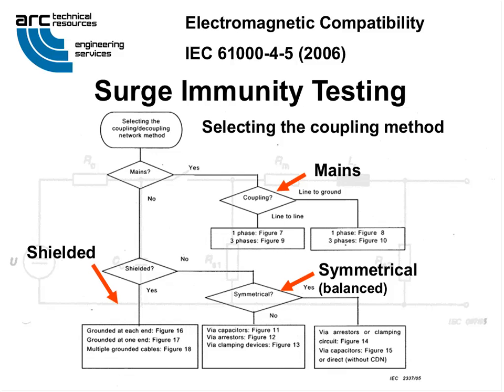The standard gives guidance on selecting the coupling method to be used. This agrees with Euronorm 55024 for computer equipment as well. Mains power is tested line to ground and line to line up to and including the test level specified. Symmetrical or balanced lines, that's telephone or Ethernet lines, are typically tested via arrestor coupling. Shielded lines are stressed through the cable grounding between products, for instance, not on the center pins.